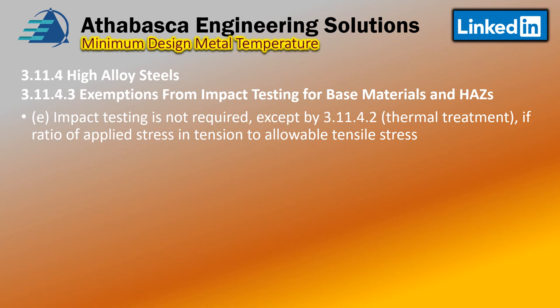Impact tests are not required — except as noted in 3-11.4.2 regarding heat treatment — if the applied stress ratio, tension to allowable stress, shows the part is not highly stressed, and you follow the heat treatment exemptions. This exemption applies to a coincident ratio of 0.3 for Class 1 materials and 0.24 for Class 2 materials within Section 8, Division 2. The applied stress is from pressure and non-linear loadings, specifically those listed in Table 4-1.1 resulting in a general primary membrane tensile stress.